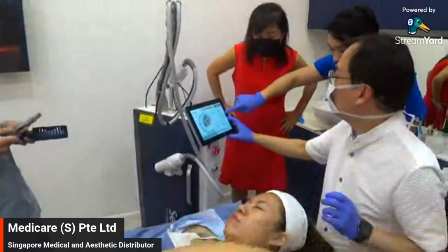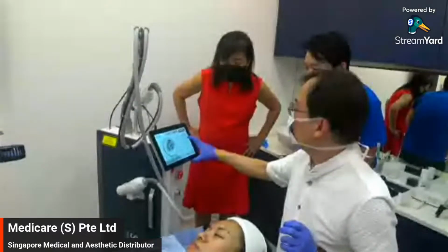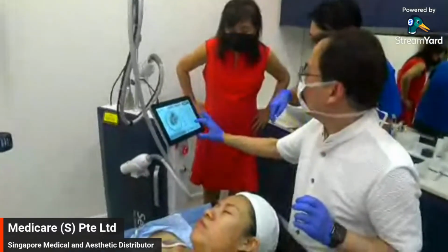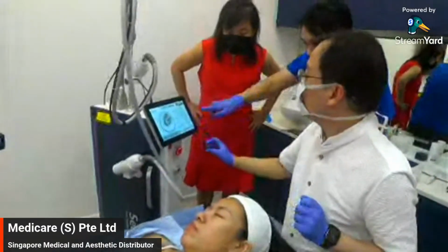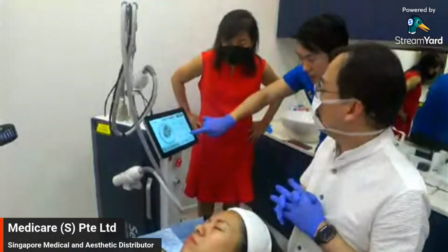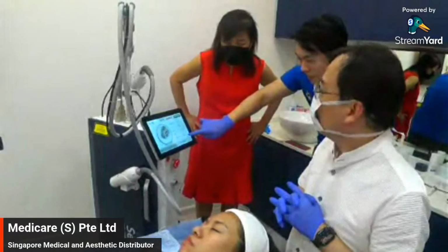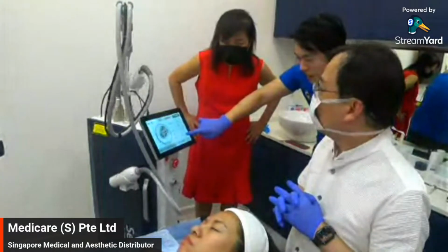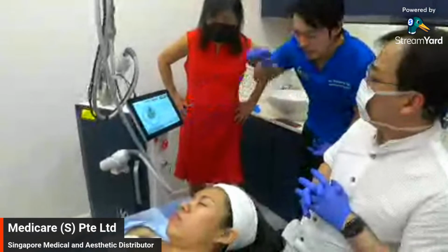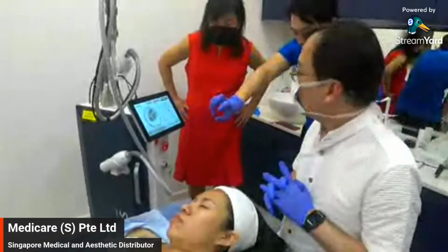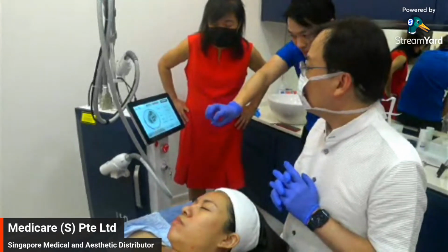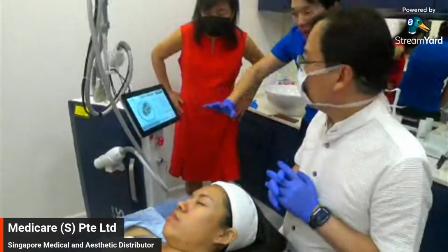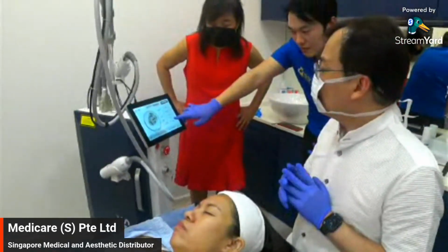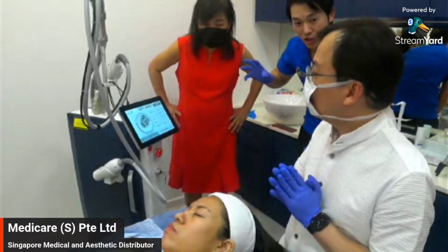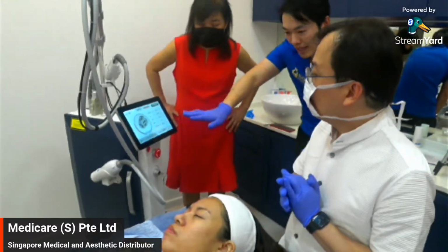Then there's a place to go to RF duration. For RF duration, just take the depth, 250. The delay time is the rest time in between, double of it, so it's 500. So basically the needle will go in, fire for 250 milliseconds, rest for 500 milliseconds, then we retract. So it's quite a long pulse. After that, there's a further delay time when the needle is retracted. This is how long we have to get to the next position.